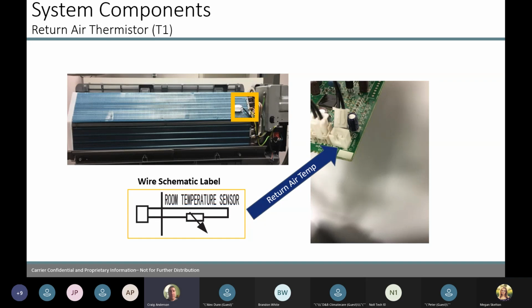Our first one is our return air thermistor. So this is the sensor that is reading the air that's coming back to this unit. So installation is a big thing. Your clearances, if it's too high to a ceiling, we're bringing a lot of hot air up there. So we need to make sure that the unit can breathe on top, that we're getting the proper airflow to it.